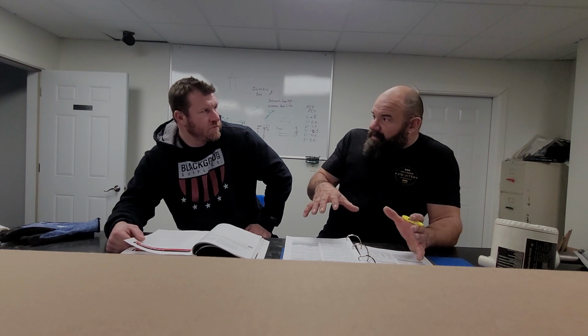By the way, people resolve that by putting Noalox so that aluminum doesn't oxidize. That's actually not needed. It has never been needed, except for a very short time in the code where actual aluminum conductors were allowed. They removed that from the code very quickly because it caused a lot of problems. What we consider aluminum conductors are not aluminum; they're aluminum alloy, and they don't oxidize. So the code doesn't say you have to use Noalox.